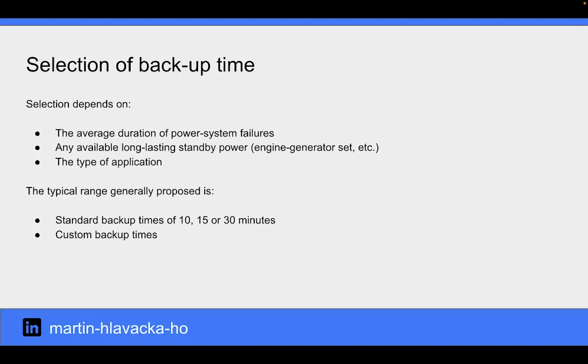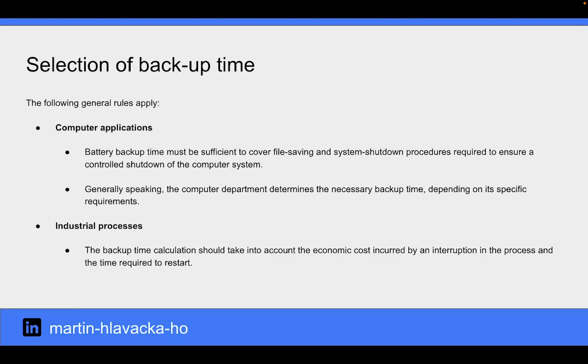The selection of backup time depends on the average duration of power system failures, any available long-lasting standby power, and the type of application. The typical range generally proposed is 10, 15, or 30 minutes, or it may be customized. For computer applications, battery backup time must be sufficient to cover file saving and system shutdown procedures required to ensure a controlled shutdown of the computer system. Generally speaking, the computer department determines the necessary backup time depending on its specific requirements. For industrial processes, the backup time calculation should take into account the economic cost incurred by an interruption in the process and the time required to restore.